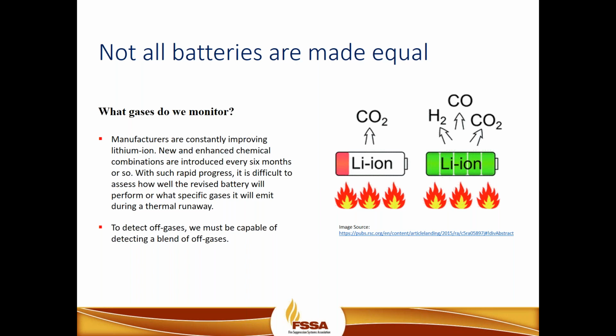And this is really where some of the codes and standards are starting to adopt new strategies at addressing energy storage systems. The chemical cocktail inside of the battery, known as the electrolyte, produces a unique off-gas that's specific to every battery manufacturer. And in many cases, the first sign of off-gassing is through a VOC, a volatile organic compound. So having a gas monitoring system or an off-gassing system that can detect both VOCs and the electrolyte chemical cocktail is critical to be able to detect off-gas.